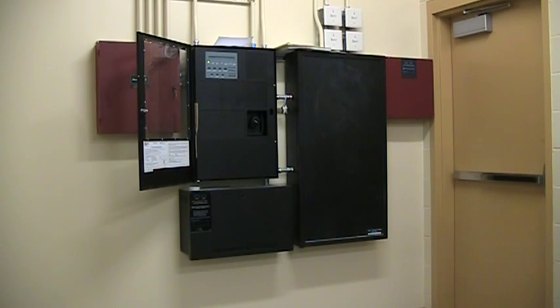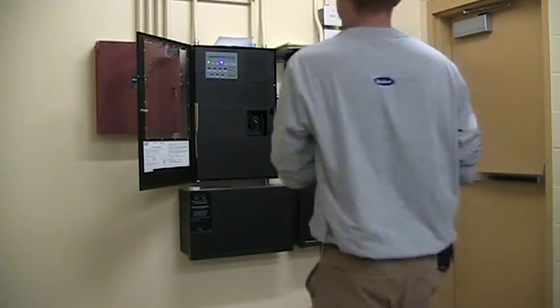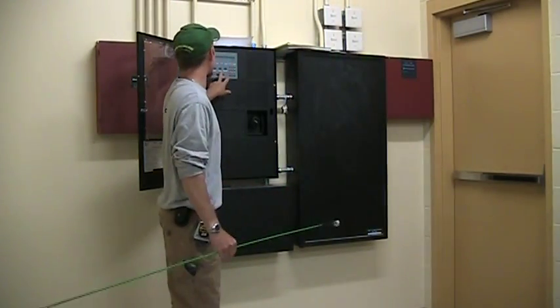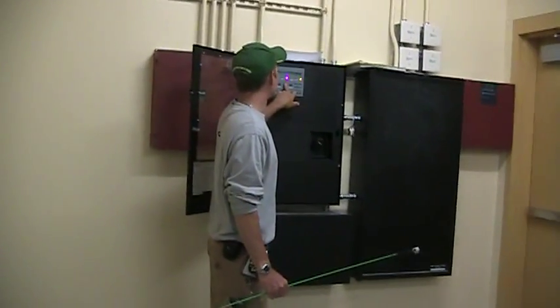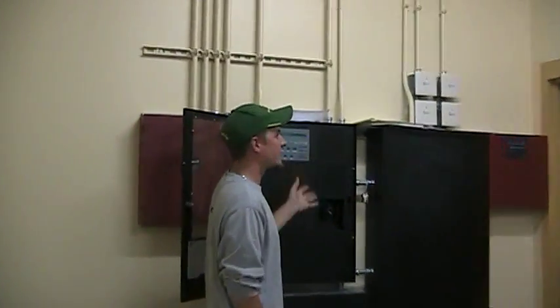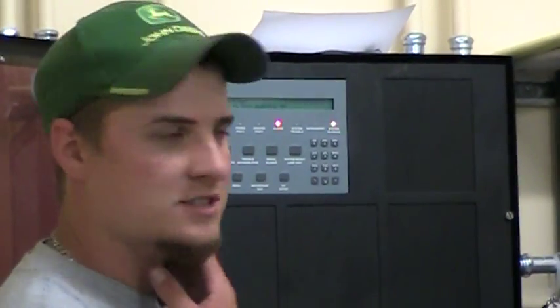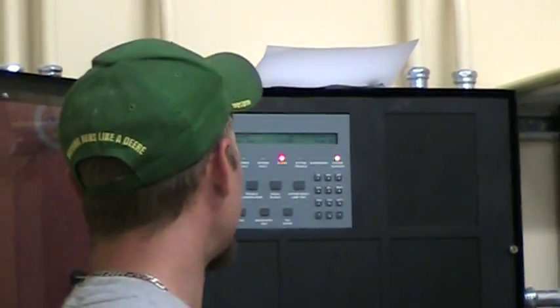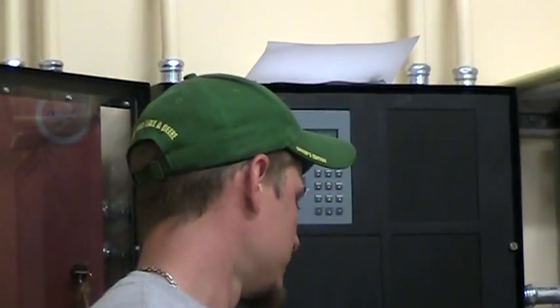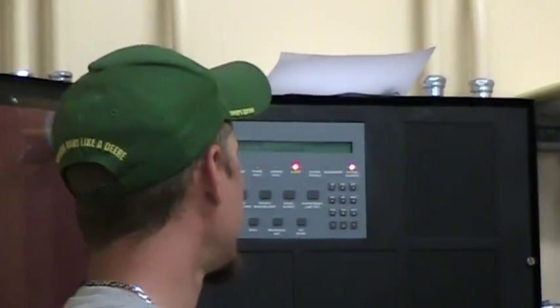Alright. The first function is silence. Signal silence. The panel is still in alarm, the system's still in alarm. Let's just silence this so you don't get the noise. If the alarm goes off, it won't reset itself. When a trouble is cleared, like say a tamper switch gets turned, it'll come in as a trouble. Once it's put back in position, the trouble will clear itself. But when the alarm goes off, it has to be reset.